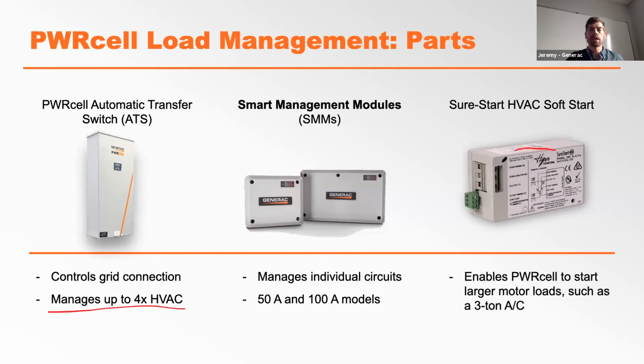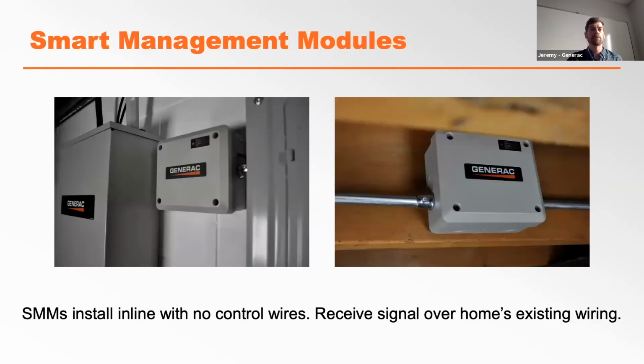Lastly, the SureStart accessory drastically reduces locked rotor amps or startup surge current for AC units, meaning that starting a 3-ton AC, even when you have base load in the home, is not going to be any trouble whatsoever for the PWRcell battery. Brings it well within the system's capability.